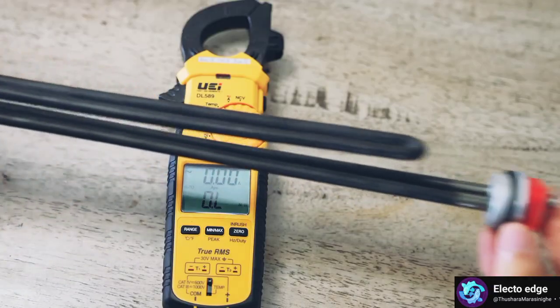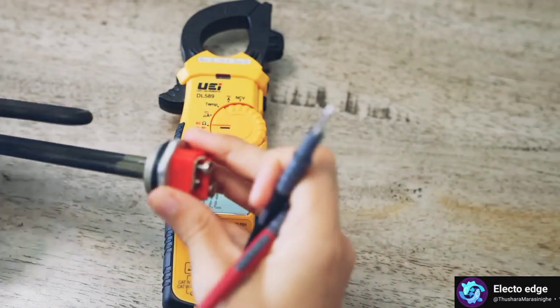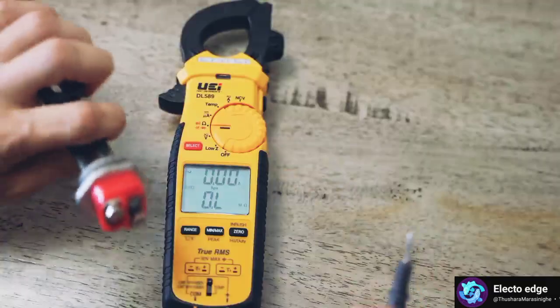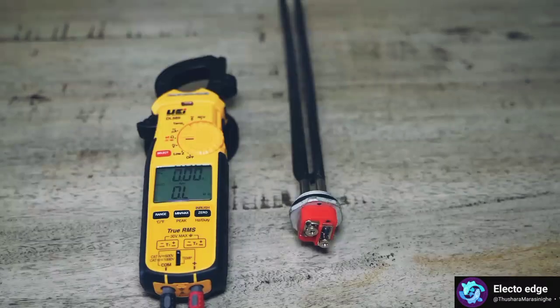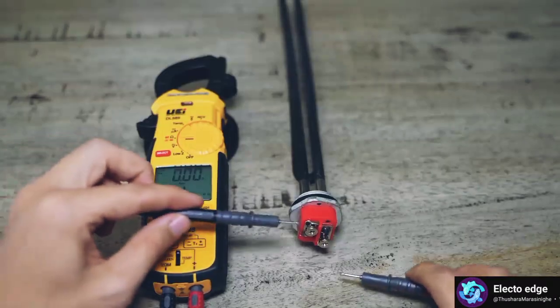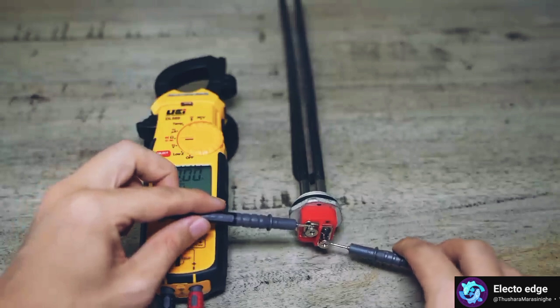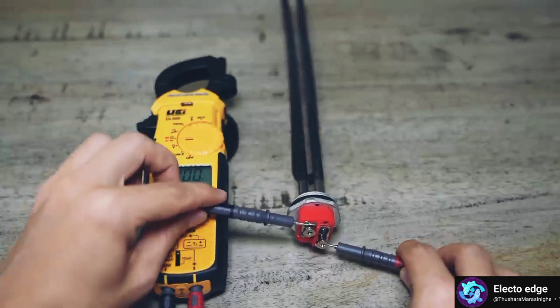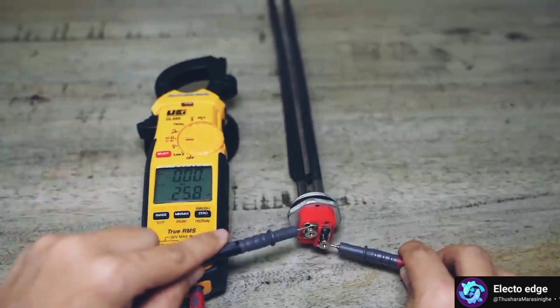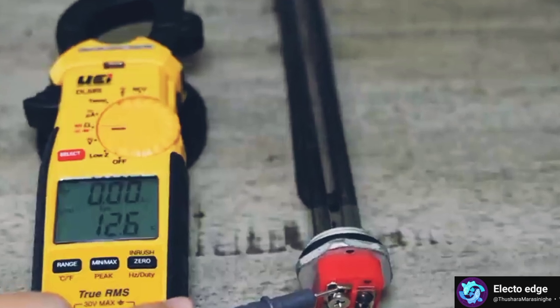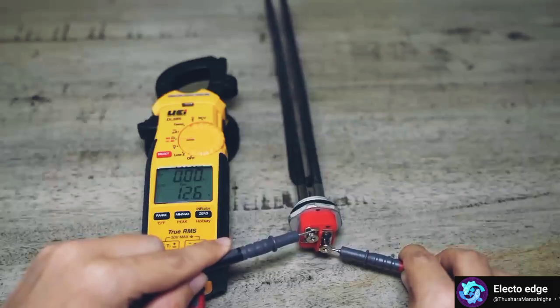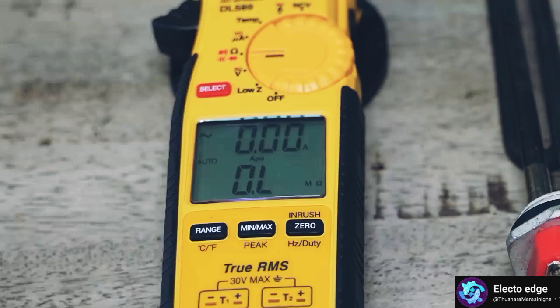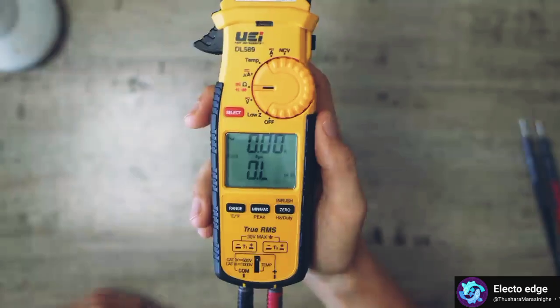Here's a water heater element, and we can use resistance to check if this element is good or not. If an element is good, the resistance on it is usually somewhere between 10 to 20 ohms. So if I put my meter leads on both screws on the element, we are getting 12.6. So this element is good. But if you had your leads on there and you were seeing OL, that means that element would be bad.